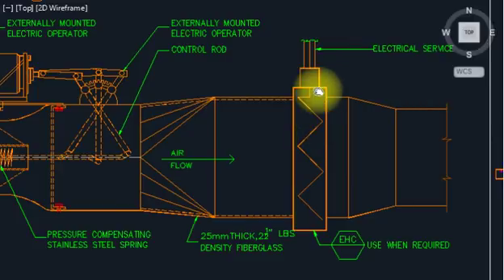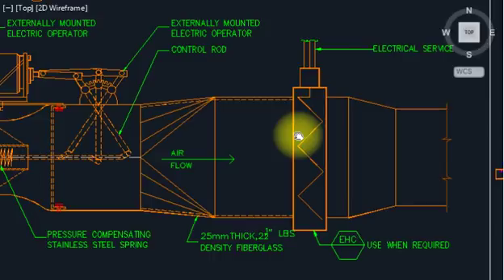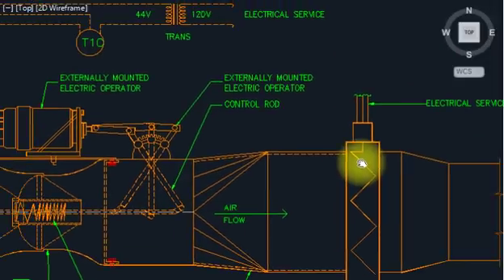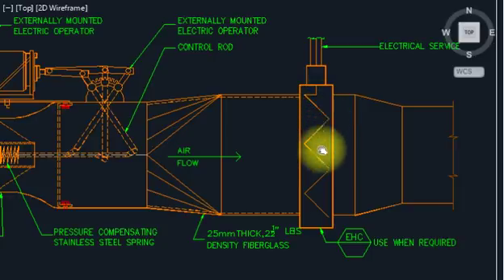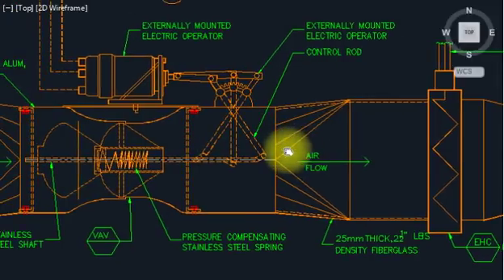This is an electric heater coil — I will zoom in on this. This is the electric heater coil inside the VAV unit. The AHU supplies only cool or fresh air. In winter, the outside temperature may be less than 22°C but we need to maintain 22°C in the room. So we turn on this heater via the thermostat, which controls the wiring to the electric coil.